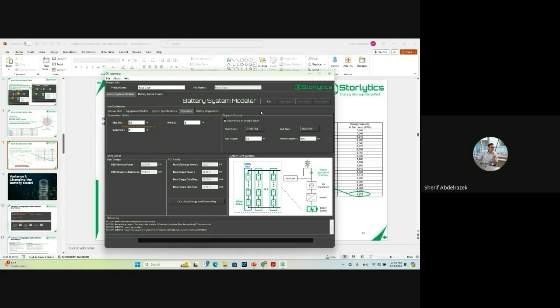So that way, every day we're prepared to charge from solar, and we don't have to tune the RTE and the battery profile creator. So let's see what that looks like here, right? You can do this on your machines as well. Just turn daily state of charge steer on. Any time period really would work that the battery's not already being used.